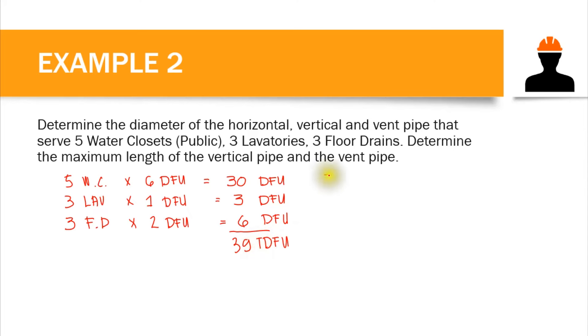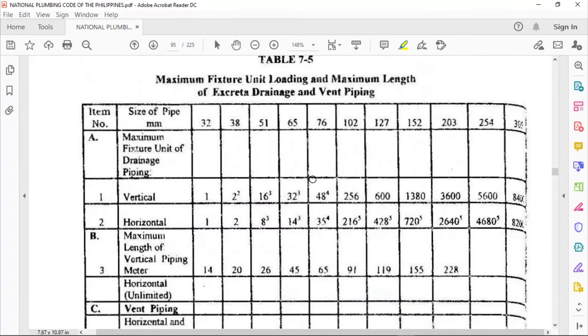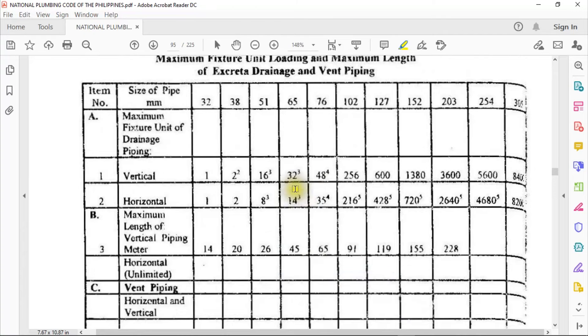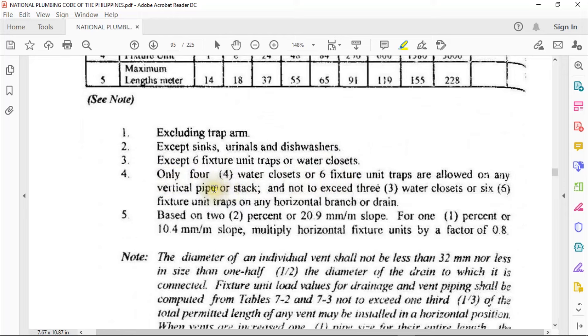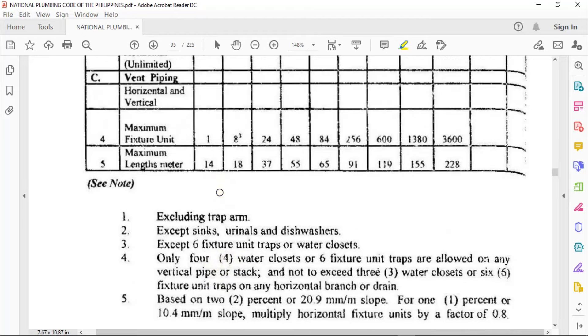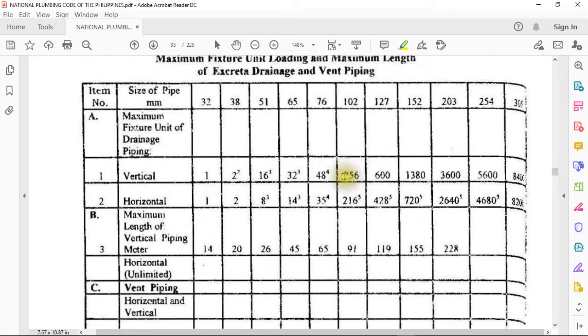We proceed to Table 7-5 with 39 total drainage fixture units. For the vertical pipe: 39 falls between 32 and 48, so we choose 48. However, 48 has superscript 4. According to note number 4 for vertical pipe, the allowable number of water closets should be less than or equal to four. We have five water closets, so we must move to the next higher value. The next value is 256, which has no superscript, so we choose it. The diameter equivalent to 256 fixture units is 102 millimeters — that is 4 inches for the vertical pipe.